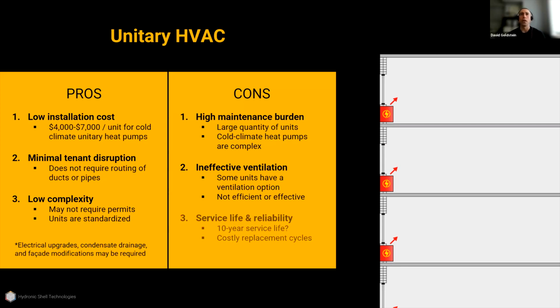And then lastly, there are issues with service life and reliability. These cold climate heat pumps are relatively new, so we don't actually know exactly what to expect for service life, but you can expect it'll be in the 10-year range, like a typical appliance, like a through-wall air conditioner or PTAC unit. So once you get this building operating, you're going to be going through expensive replacement cycles. Once you get 10 years into your retrofit, you're going to have to start replacing these units, and that's just going to be an ongoing expense that's really problematic, especially given how expensive these units are. So unitary is great from a first cost, installation perspective, but it's really problematic from a life cycle, long-term cost perspective.